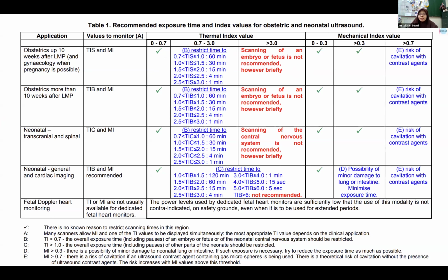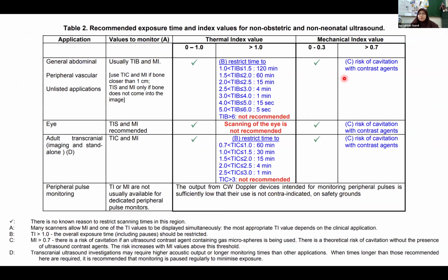And then these are the mechanical values. If it is above 0.7, then you could have a risk of cavitation, especially if you're using it with a contrast agent. The fetus is more sensitive, but for non-obstetric or non-neonatal ultrasound, you can see that the TI values are a bit higher. So if it is more than 1.0, only then do you start to restrict the time. And the risk of cavitation also increases compared to when you do imaging on the fetus.